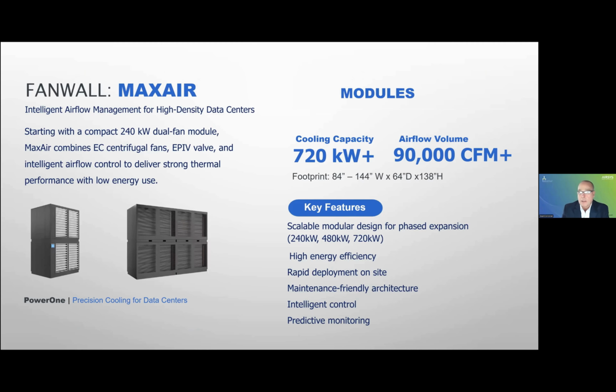Our fan wall, the Max Air. Again, this is another product that is scalable. It comes shipped in 2 different pieces. It has quick connect, low voltage electrical components, so you can easily put them together. There are some high voltage connections that need to be made by a certified electrician. However, this design and this modularity gives us the ability for rapid deployment. It's maintenance free. It comes with Carel controllers for monitoring. The cooling capacity is 720 kW plus and over 90,000 CFM in a small footprint ranging from 84 inches to 140 inches wide with standard depths and heights.